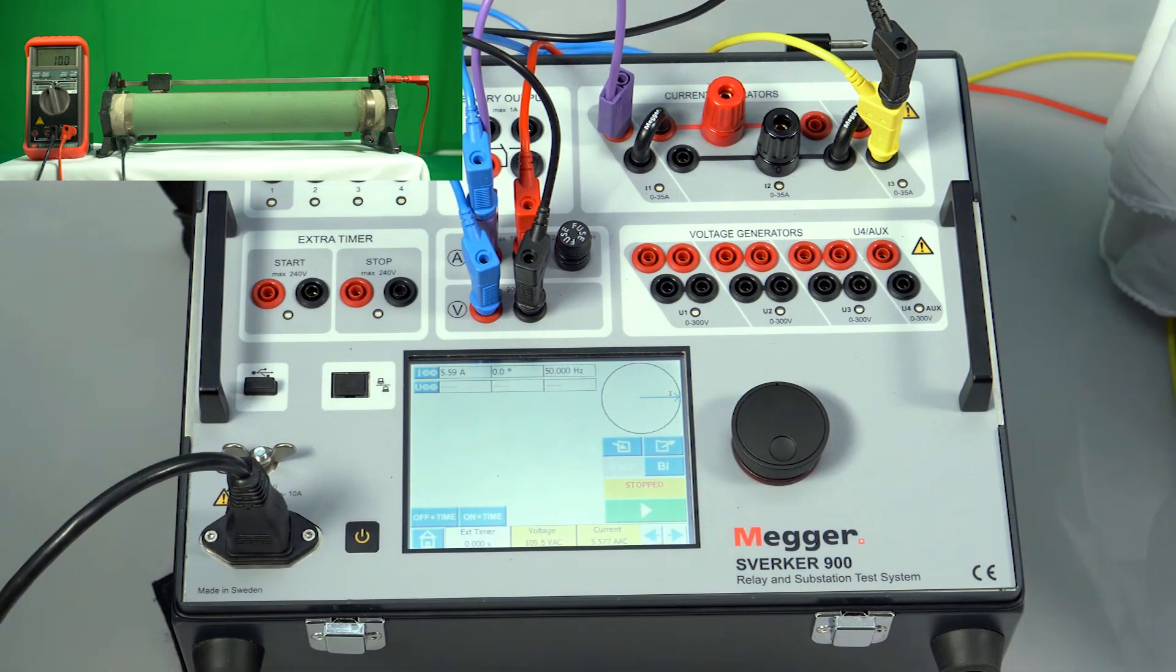The compliance voltage is 109.5. The current measured is 5.577. The resistance is 20 ohms, hence the power is 622 VA which is in line with the specification.